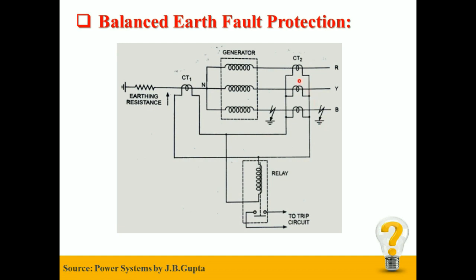Under normal working condition, the current flowing in the secondaries of the line CTs sums to zero. Also, the current flowing in the neutral CT is also zero, and so the relay remains de-energized. But when an earth fault occurs within the protection zone, the fault current flows through the primary of the neutral CT, and the corresponding secondary current flows through the relay operating coil. Therefore, the relay gets energized and sends a trip signal to the circuit breaker in order to protect the stator phase winding of the three-phase generator against the earth fault.